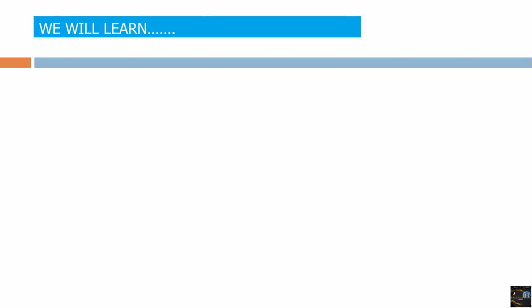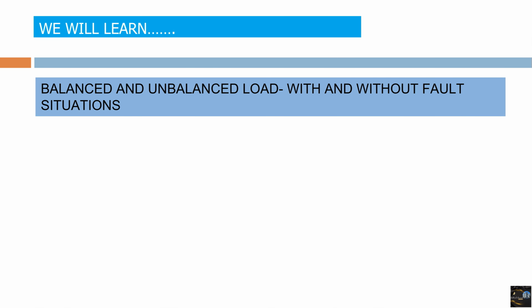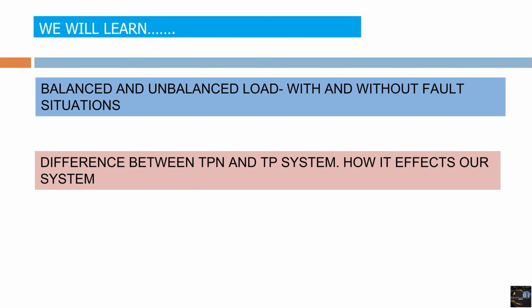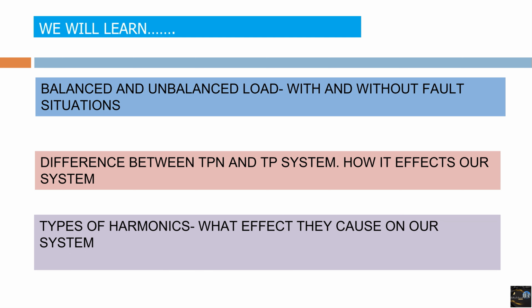So in this section, we will learn balanced and unbalanced load under both conditions, that is with fault condition and without fault condition. Then we will see the basic difference between TPN and TP system and how it affects our system if we don't care about this system. And then we will see types of harmonics. This is very important because in every electric system we have to take care about the harmonics, especially when we are talking about high voltage or medium voltage and what effect they can cause on our system.